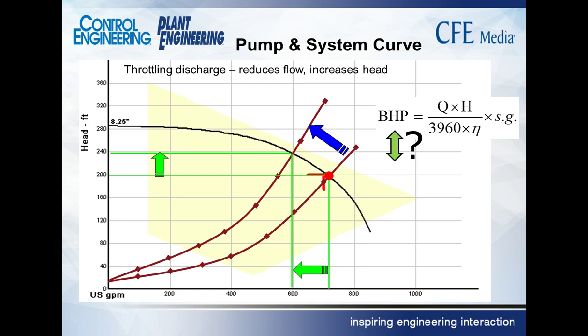Well, we did reduce the flow. We moved it up the pump curve. We changed the system curve to move the operating point back up on the pump curve. To do that, we reduced the flow, but we increased the head. Well, if we reduce the flow and increase the head, what do we do to the amount of power that's required? We had a formula for that. It was flow times head. One went down, one went up.